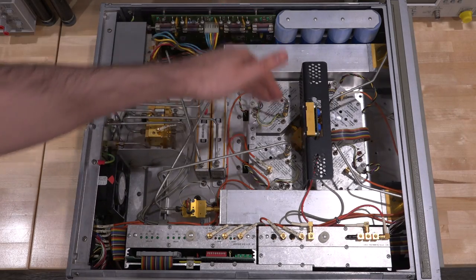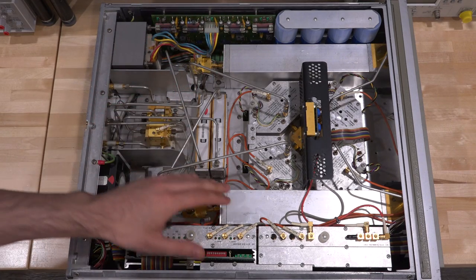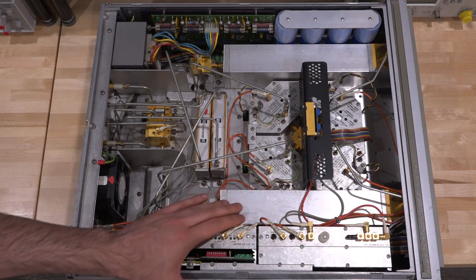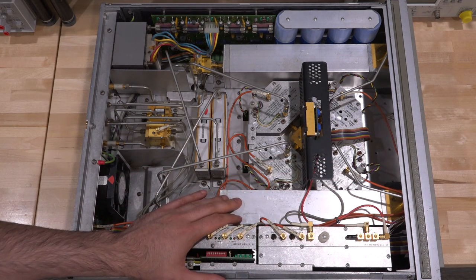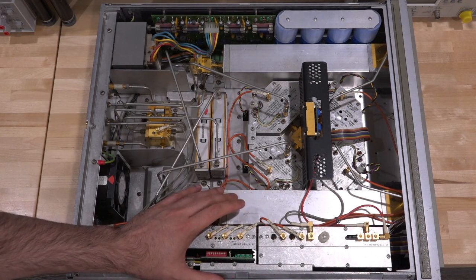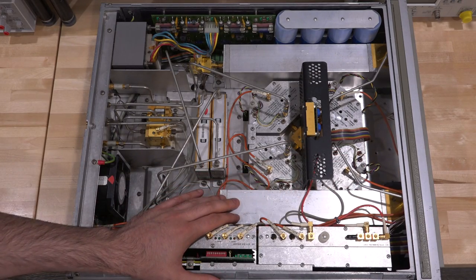From a global point of view, this instrument is supposed to be able to down-convert four RF signals individually and use some calibration coefficients and mathematics to derive the S-parameters. So here is port one, here's port two, and this massive rectangular piece must be the coupler. It's much larger than I anticipated given that it only goes down to 40 megahertz.